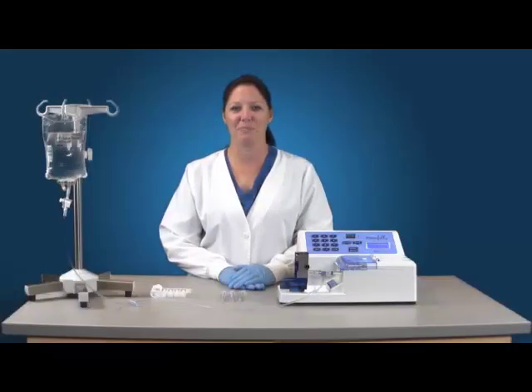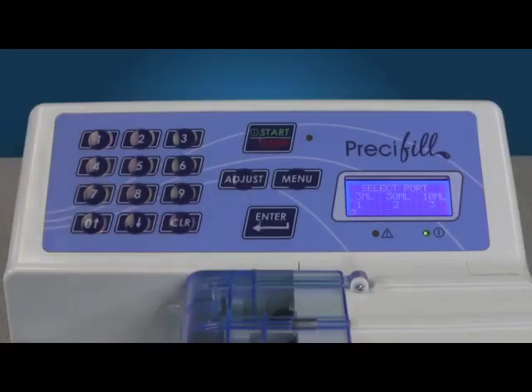Automatic filling allows you to program the number of items to be filled, for example 100, and the time interval between fillings, for example 3 seconds. The benefit of automatic fill is it prevents the user from having to manually press the Start-Stop button each time they load a new syringe or bag. Select number 1 for New Setup. Select the port being used.